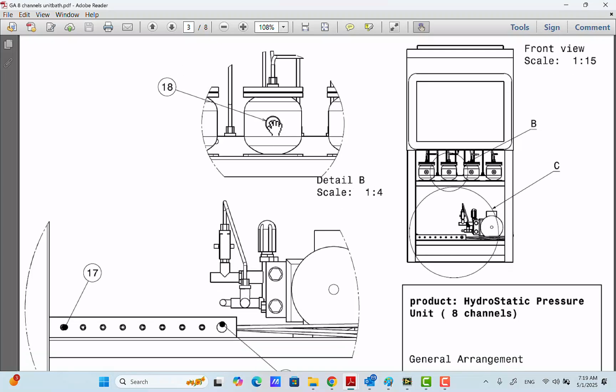The presentation here. Also, there is one more point here. On the back side of the accumulators, you have a connection for the charging of gas, nitrogen gas or air, inside the accumulator to set the pressure to the proper level for our use. This connection is the standard connection for the accumulators. I mean, if you buy a kit for the charging of the accumulators, you will have this connection inside that kit. This is a standard part. You can also buy it from the sales team of the company, or you can buy it locally. As I said, it is a standard part, a standard unit named charging kit for the accumulator.